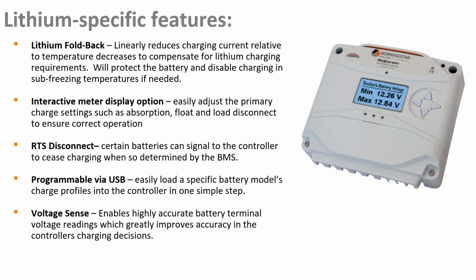And that's very good because it can keep the batteries operating at an optimal temperature where you can continue to allow charging. For other instances where you're reaching a low temperature threshold, where again you're risking damage to the battery, you want to be able to taper the charge current by the external charging device, that being our controller.